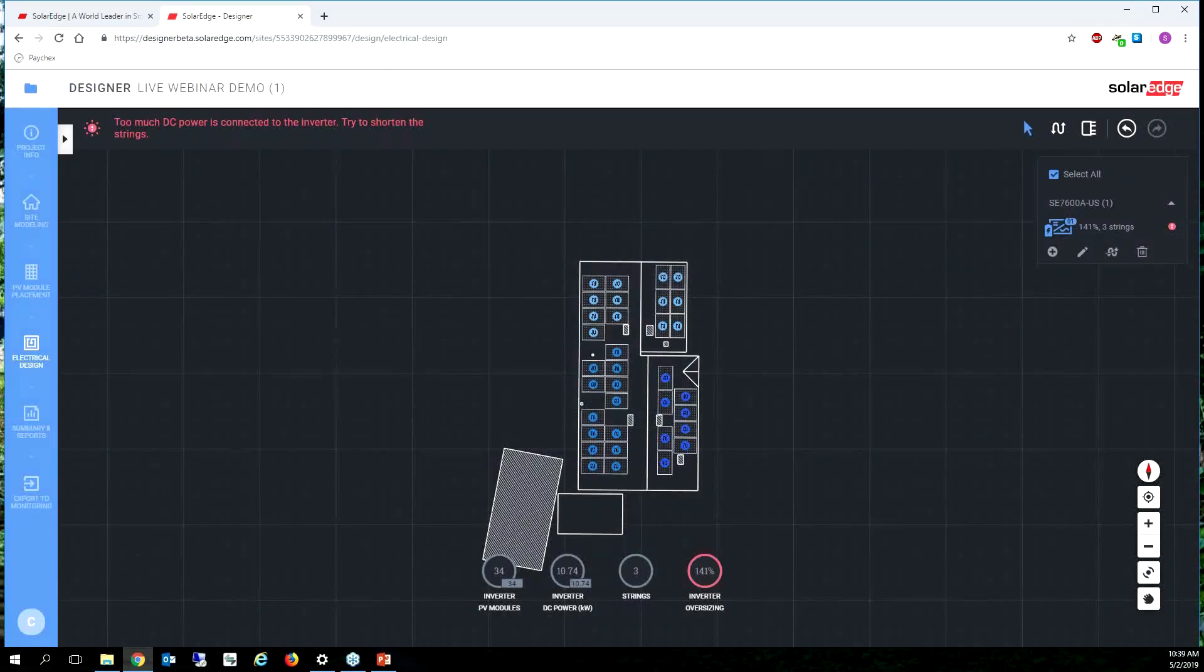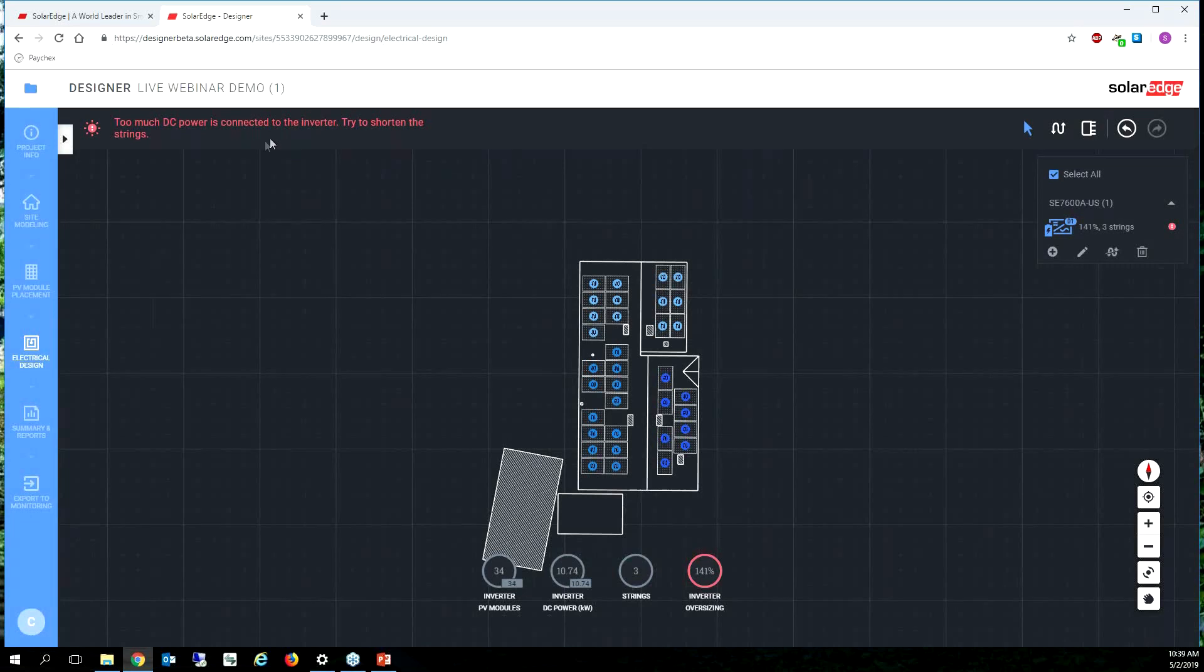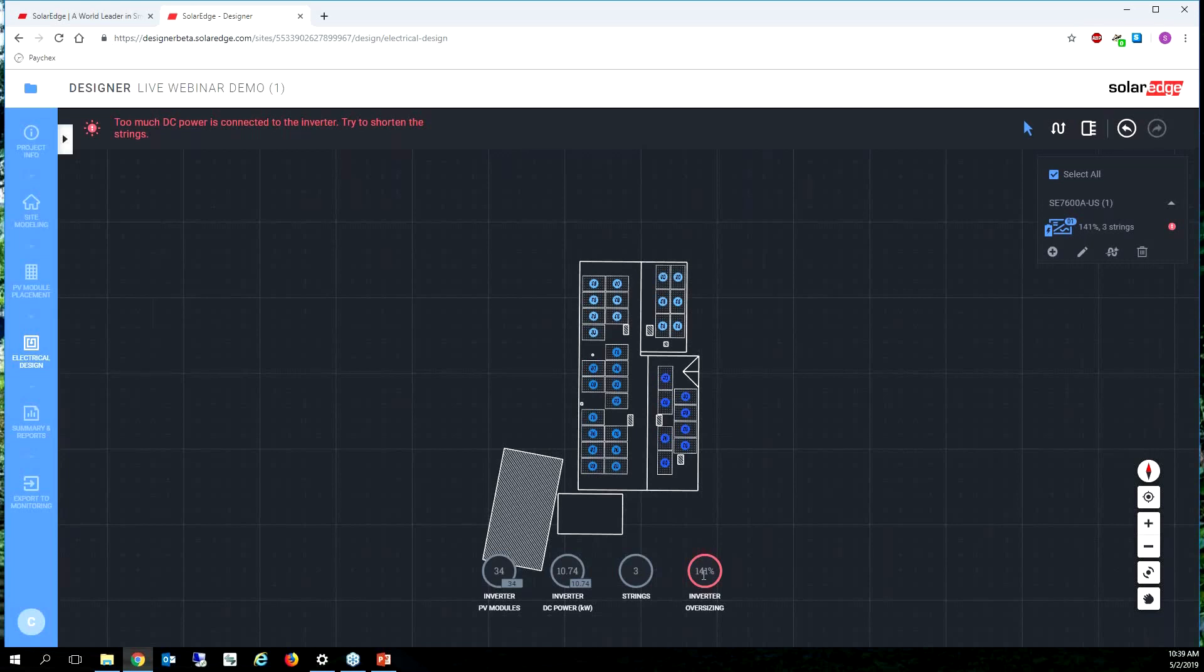I'm going to click done. All right, the tool is giving me an error and it's saying too much DC power is connected for this inverter. So I have 141 percent DC to AC ratio and on the storage inverter, the 7600A, the maximum DC to AC ratio is 135 percent so I'm going to have to remove some modules.